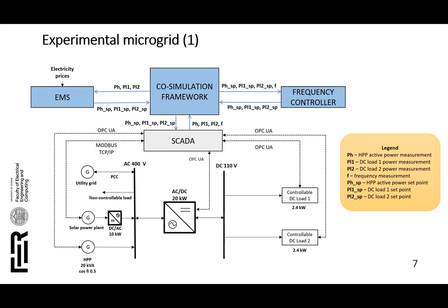All components have been integrated into a laboratory SCADA system with different communication protocols. The main component of our hierarchical control scheme is a flexible smart grid simulation framework called mosaik. mosaik coordinates execution of all controllers at all levels and controls data exchange between them. The upper and lower optimization levels are directly connected through the co-simulation framework, while the local plant-level controllers are integrated through the existing SCADA infrastructure. SCADA is connected to mosaik using a TCP-based gateway.